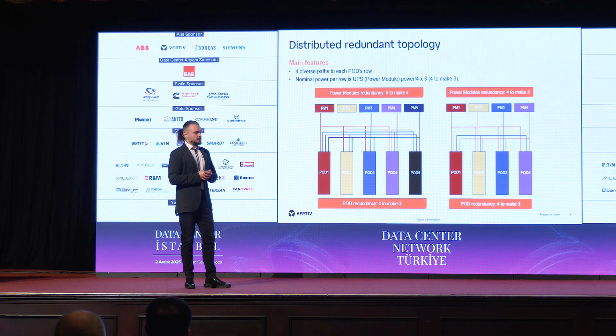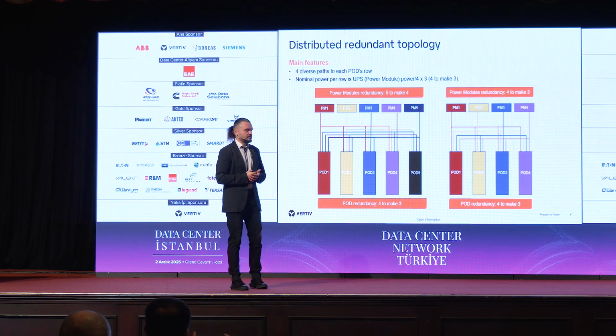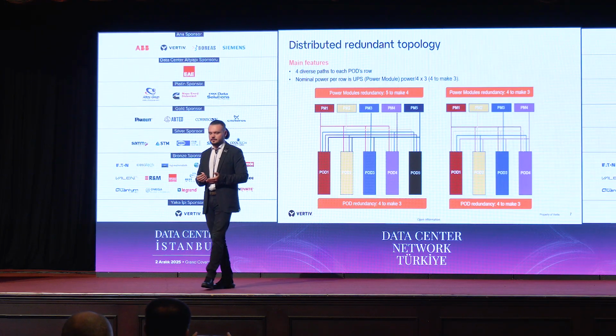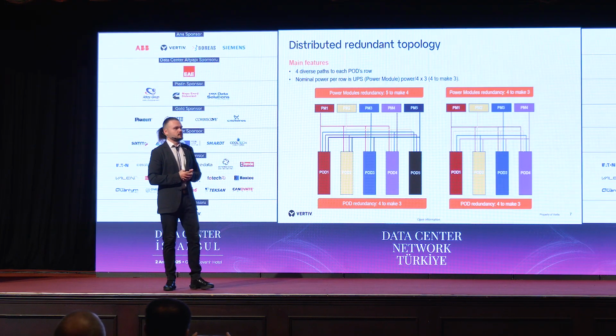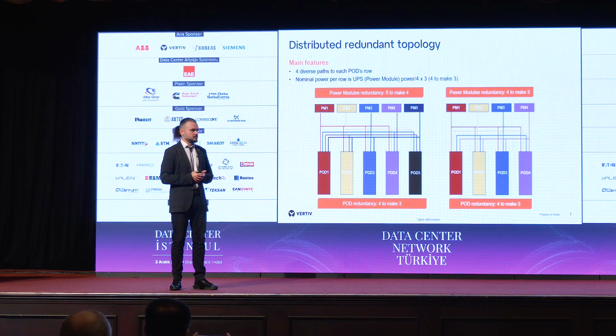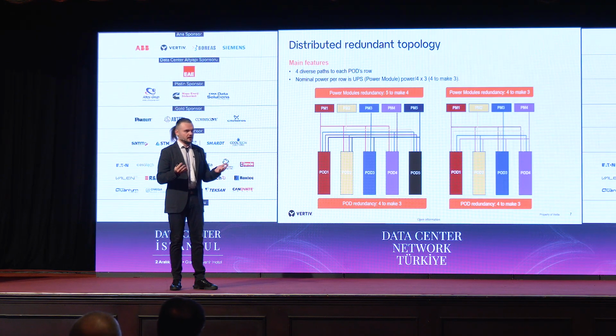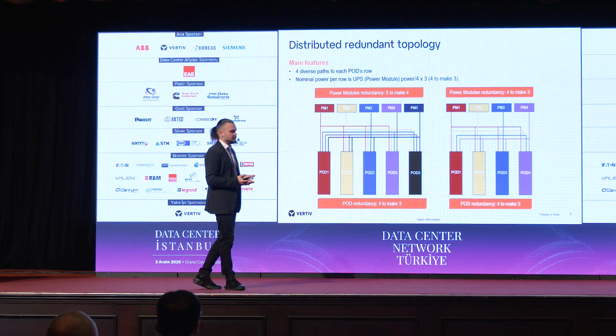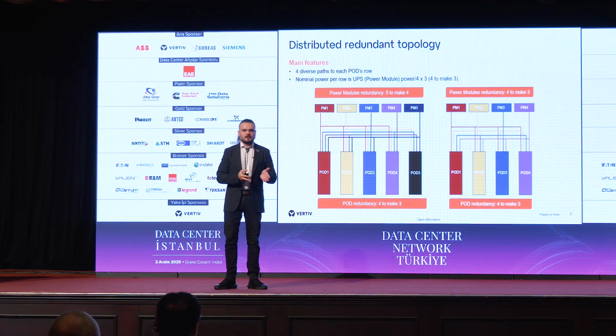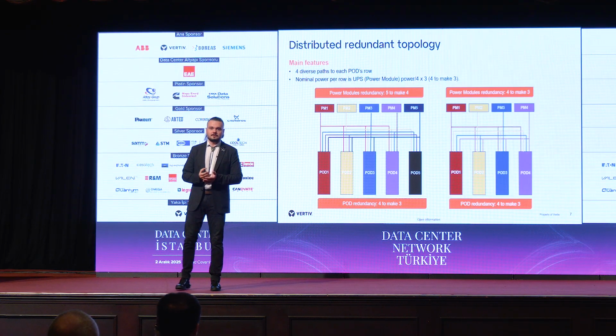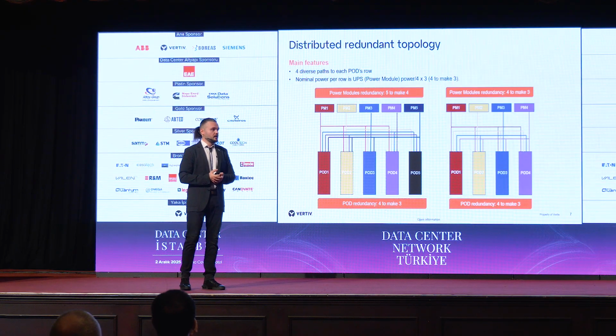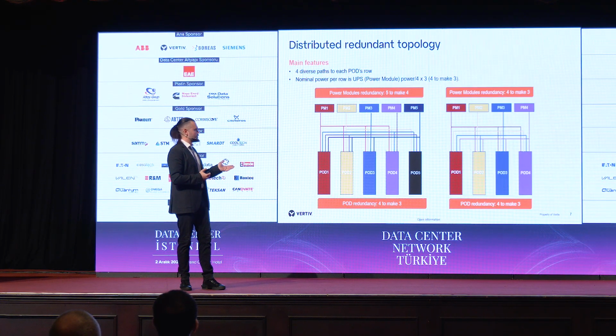What is special about the topology? The power topology has changed, let's say, dramatically. All the colocators and hyperscalers used to have the block redundant topology, and for most cases it's more than enough. If you have an A plus B feed, it's okay to use STS switches, UPSs, and catcher UPS. But it no longer works in the AI world, so we are basically making our topology based on distributed redundant.